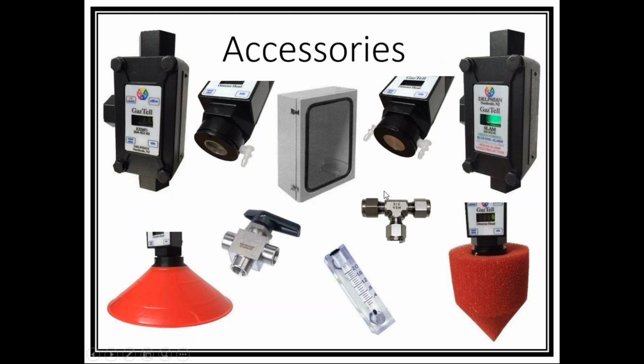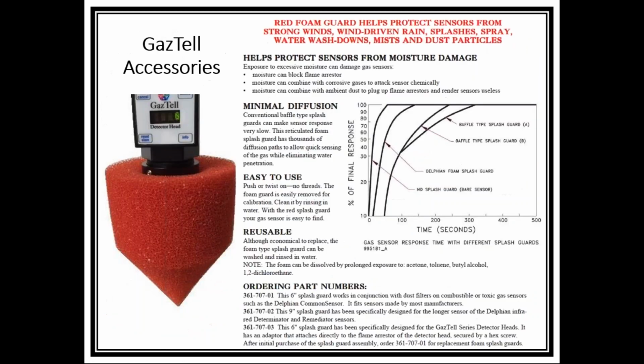We can also do sample draw systems, which consist of a rotometer, an eductor, and a 3-way valve, so you can switch it between the sample location and the calibration devices. We have other accessories such as the foam splash guard, and the sealing cone, which allows accumulation of gas into the detector head.